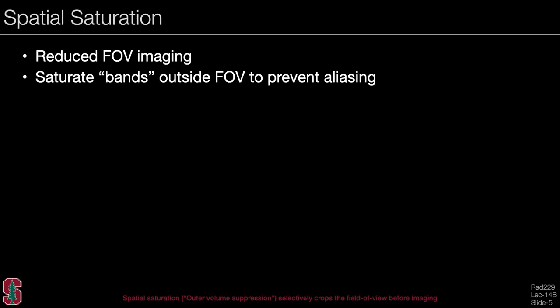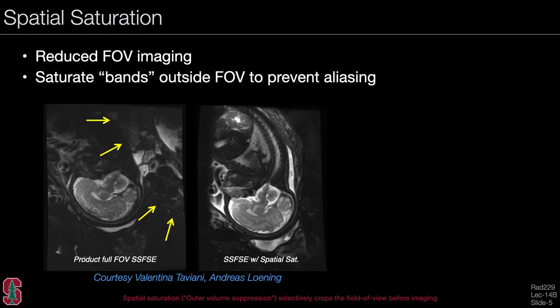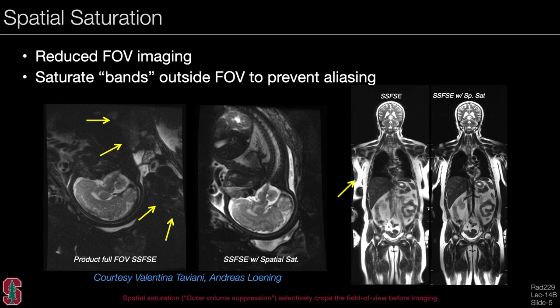Another common form of saturation is a spatial saturation approach. Here we want to do reduced field-of-view imaging because it may be faster. We saturate bands outside of the field of view to prevent the signal from these bands from aliasing into the field of view. For example, in a fetal image, using a spatial saturation band on the left with a single-shot spin-echo, we can remove signal coming from the mother's body that might otherwise obscure the fetal image. Similarly, if the arms are aliasing into the image, applying a spatial saturation outside the body removes this aliasing. So spatial saturations are generally used to prevent some kind of aliasing effect.